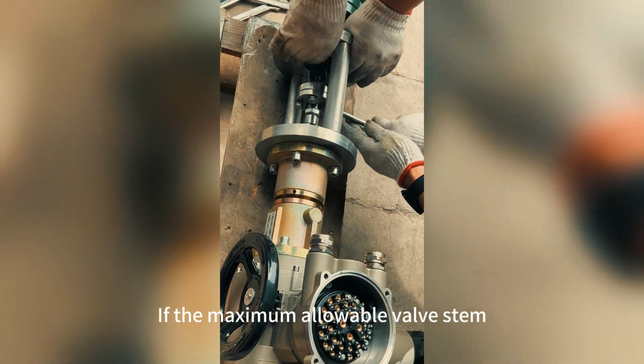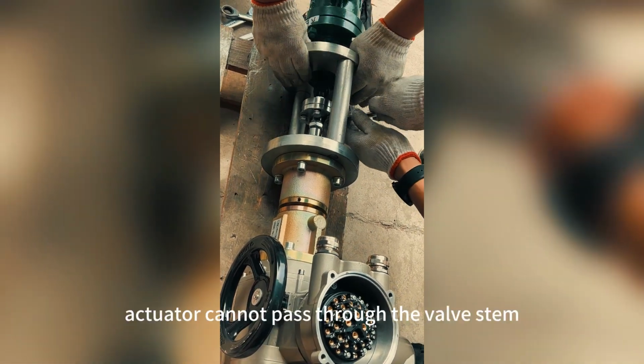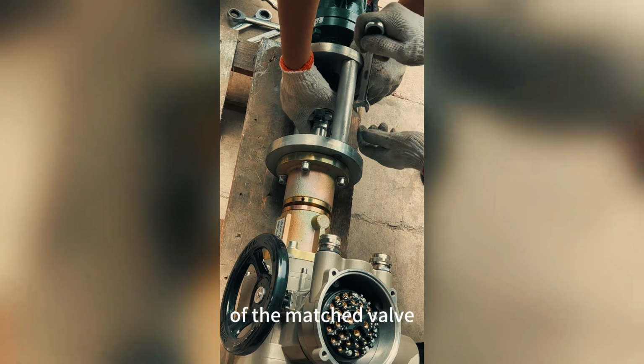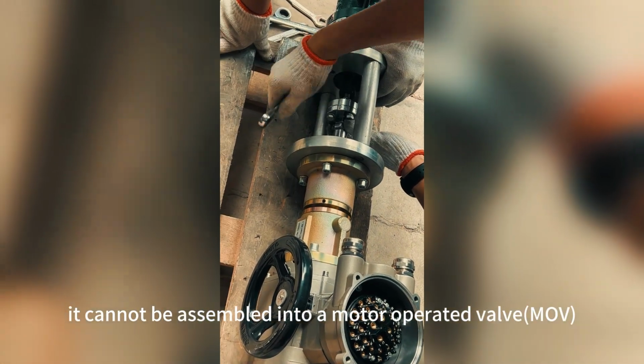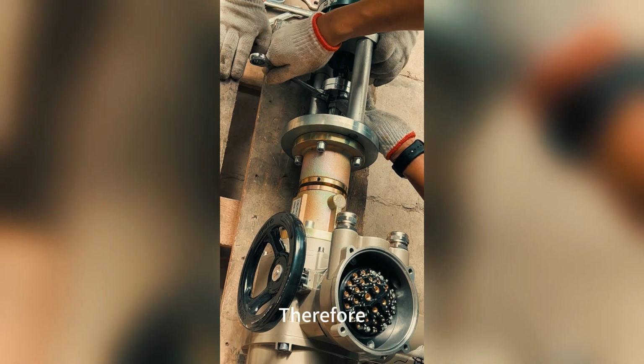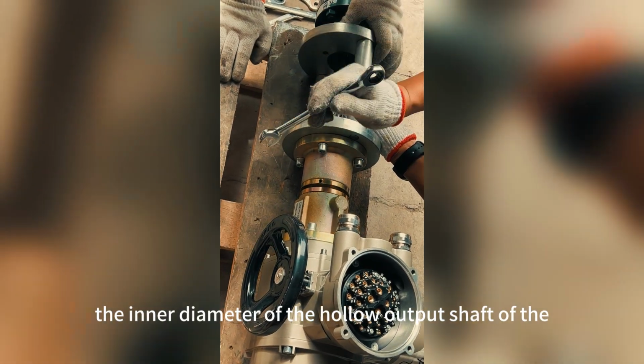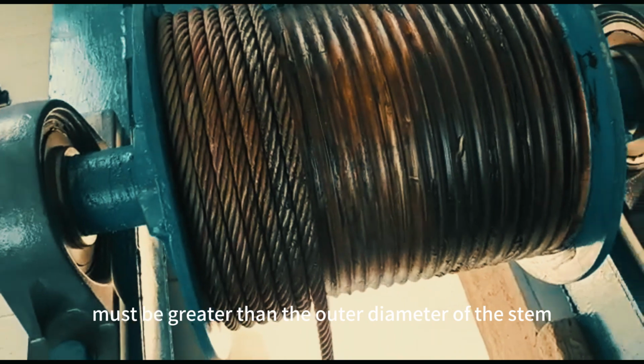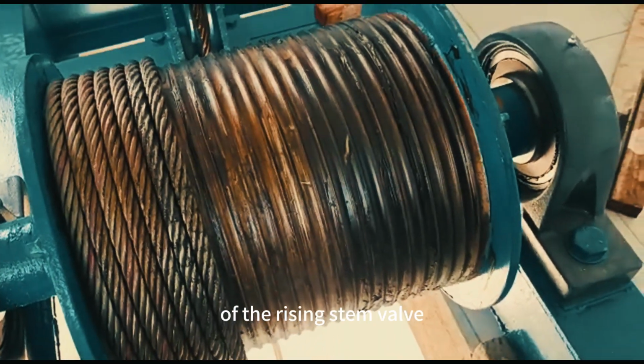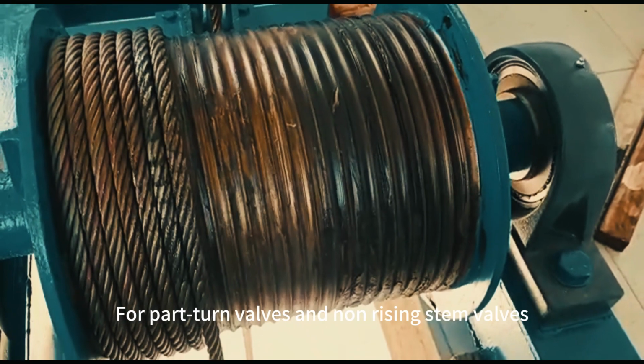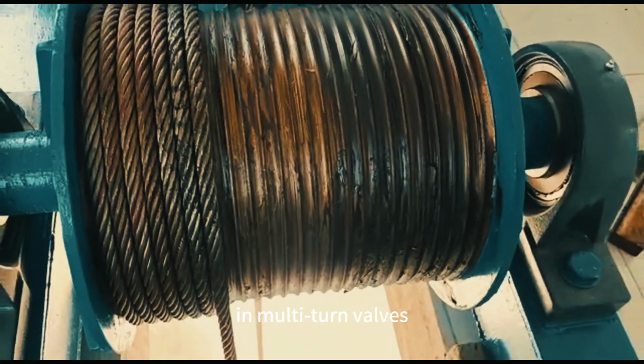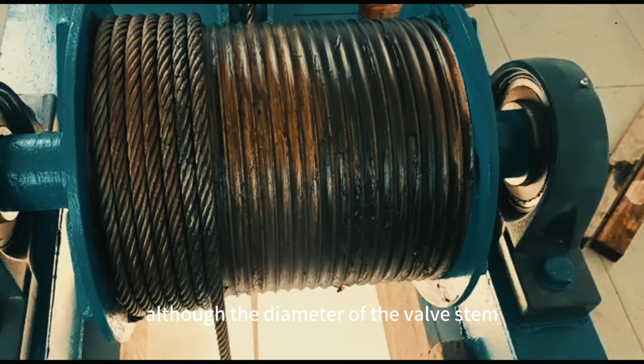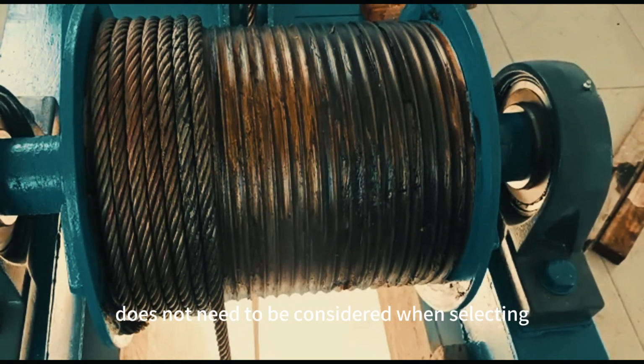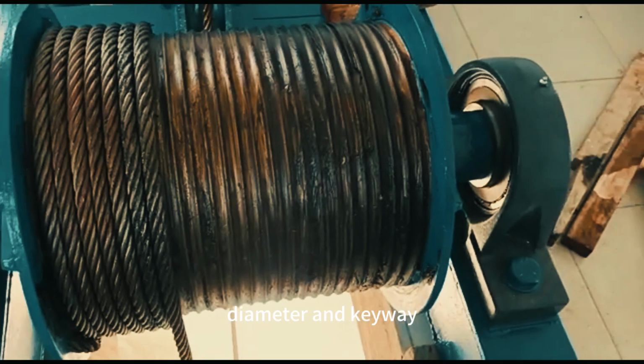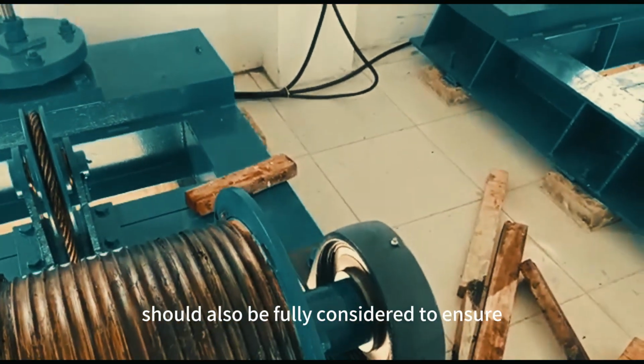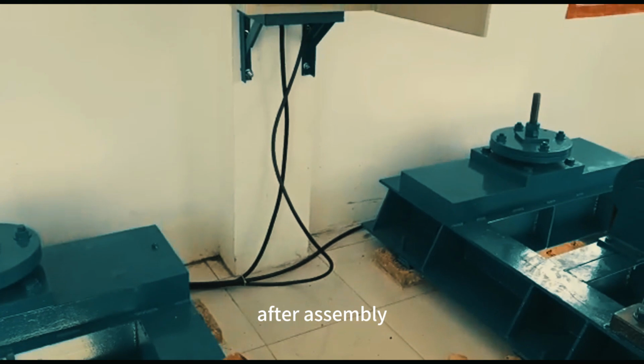If the maximum allowable valve stem diameter of the electric actuator cannot pass through the valve stem of the matched valve, it cannot be assembled into a motor-operated valve. Therefore, the inner diameter of the hollow output shaft of the electric actuator must be greater than the outer diameter of the stem of the rising stem valve. For part-turn valves and non-rising stem valves in multi-turn valves, although the diameter of the valve stem does not need to be considered when selecting, the size of the valve stem diameter and keyway should also be fully considered to ensure normal operation after assembly.